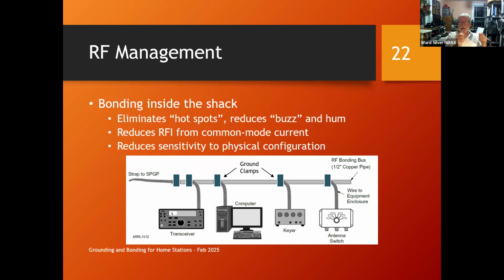If you open up the panel and take off the protective cover, you'll see these big bars at the side of the box where the neutral wires and ground wires go. You can buy smaller versions of that for a few bucks at the hardware store, with weird numbers of connections like 5, 7, 9, 13, 29. Take one of those and bolt it to your desk on a piece of aluminum flashing, and it's perfect for grounding all your ground connections from your equipment.